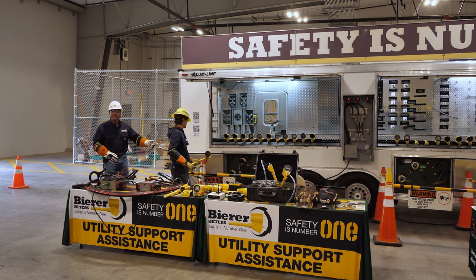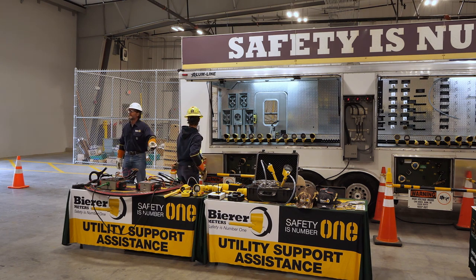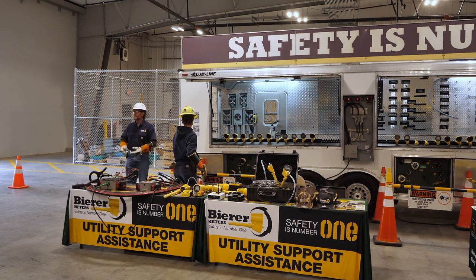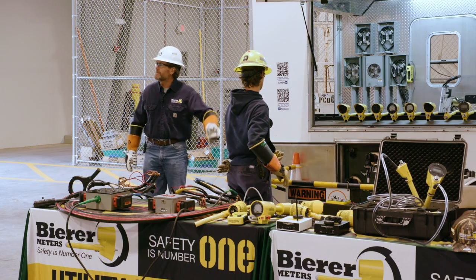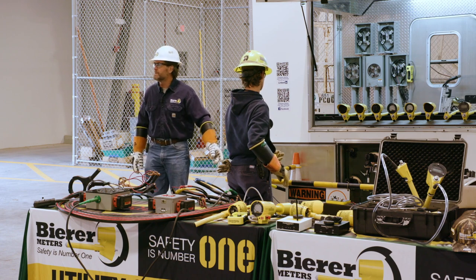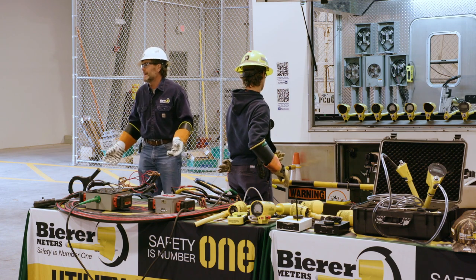If we're out of phase, we'd get close to 500 volts, way higher than the phase to ground reading off of any of those elbows. That means you're out of phase. You don't even need a calculator.